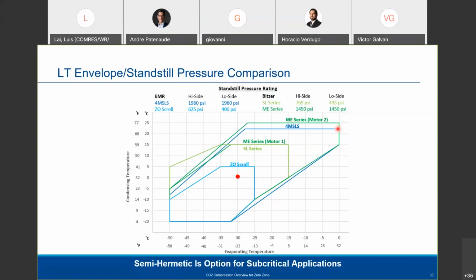The Emerson one, the 4 MSL that I just showed you, our semi-hermetic version, has a much wider operating envelope than the scroll. But again, you need to ask yourself, where are you operating? Do I fit within the operating parameters of that system? And in refrigeration, you're always within that range.